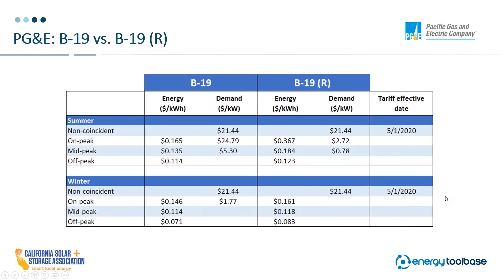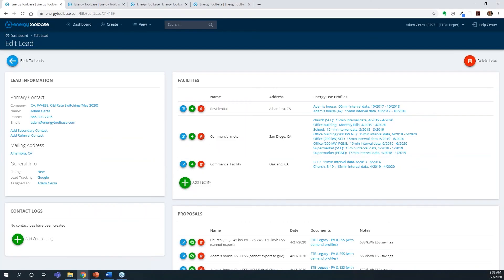Very quickly, I threw in a PG&E rate just to make sure I'm covering everybody. This is the B19 moving to the B19 option R. This one doesn't have as strong an effect as the last two — basically the on-peak summer demand goes from about $25 per KW down to about one-tenth of that when you move to the B19 option R. But you can see similarities between all three of these rates, and that's the setup as I now jump into some case studies where we found some super interesting results — and this is actually the first time we're sharing a lot of these findings.